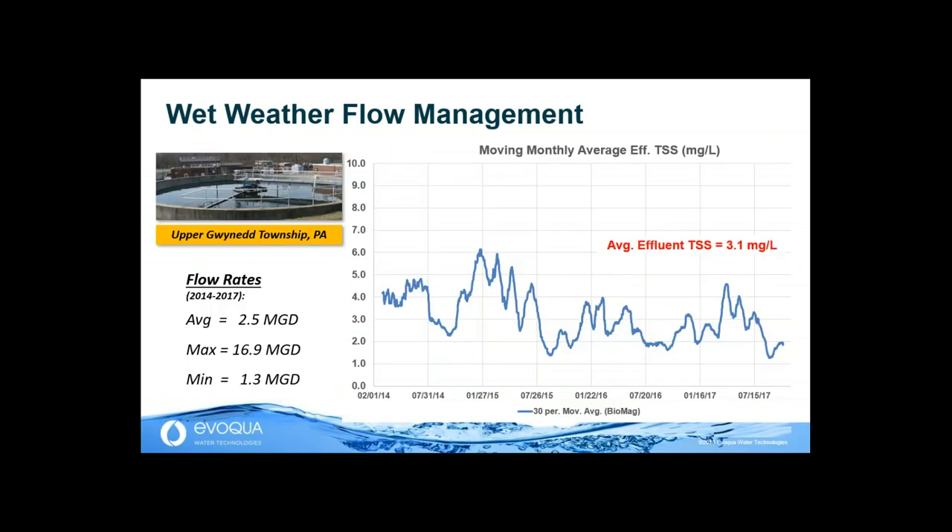Now let's move to wet weather flow management — a challenge for our industry, because when it rains, it pours. Upper Gwynedd Township, Pennsylvania has been running with Biomag since early 2014. The main challenge was high peaking factors. Between 2014 and 2017, the flow rate showed a very high peaking factor, with a maximum peak flow of 17 MGD and an average of 2.5 MGD. Regardless of these hydraulic surges, the effluent TSS out of the secondary clarifier was pristine — a monthly moving average effluent TSS in the single digits, with an average of less than 3.1 mg/L.